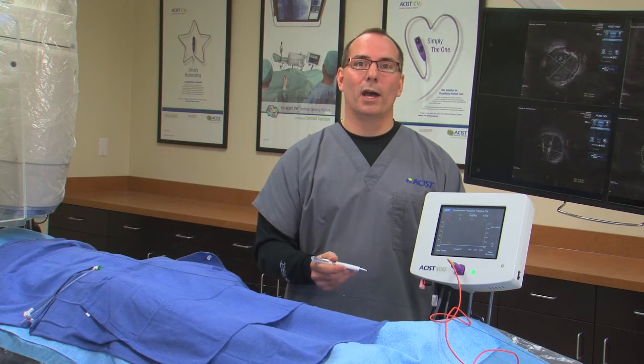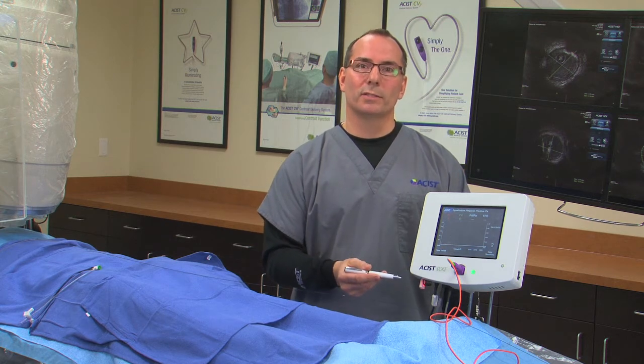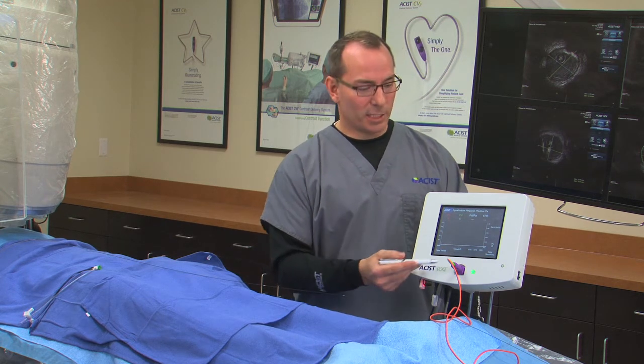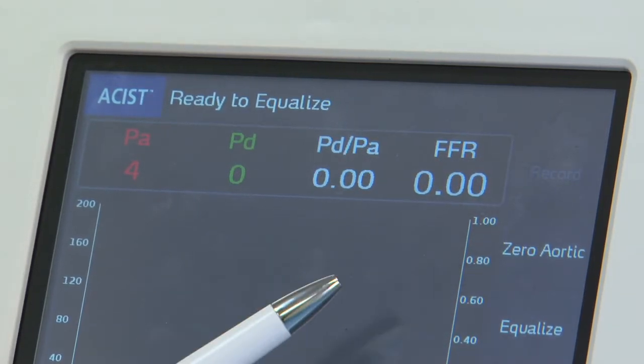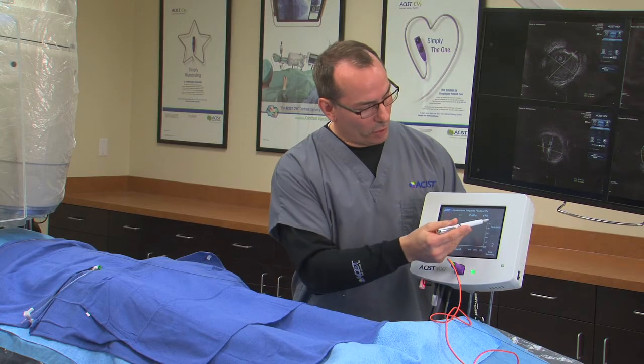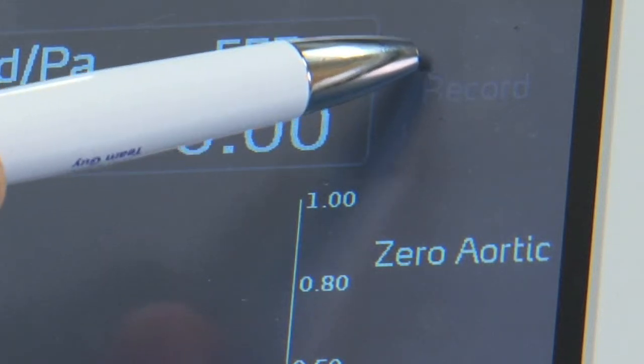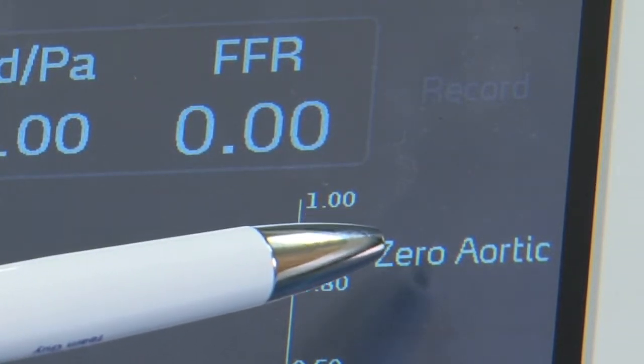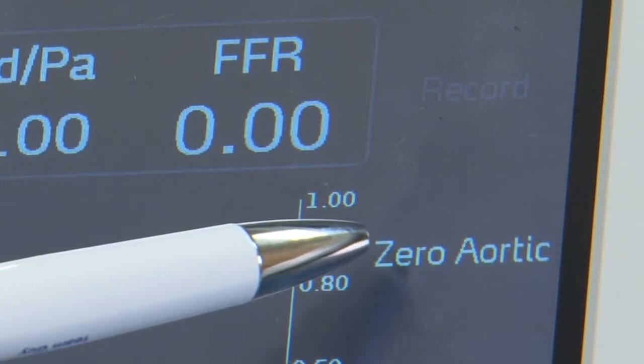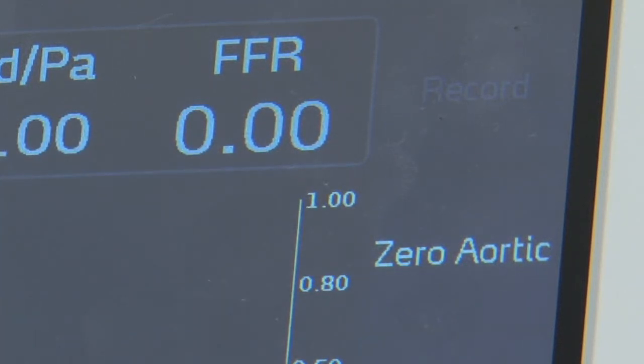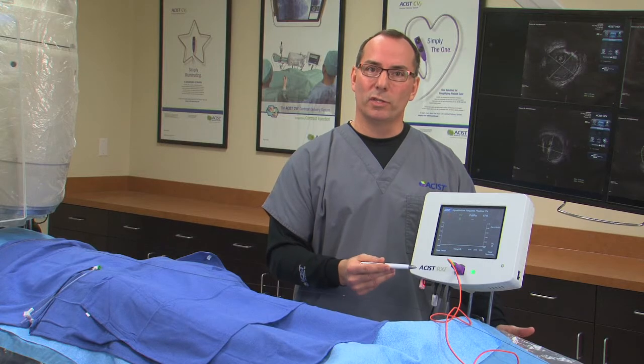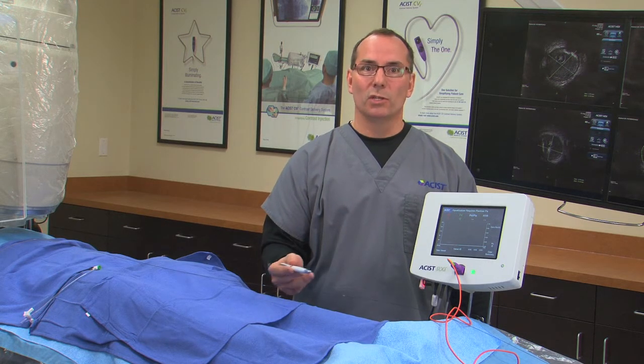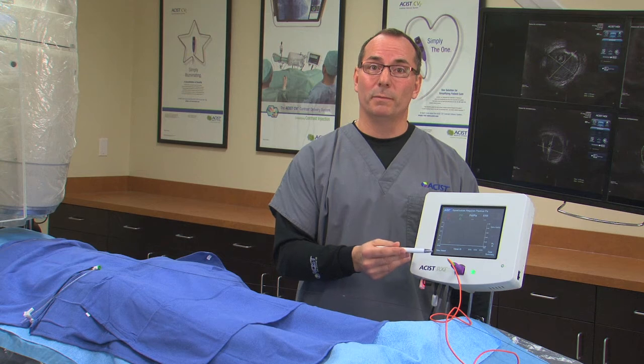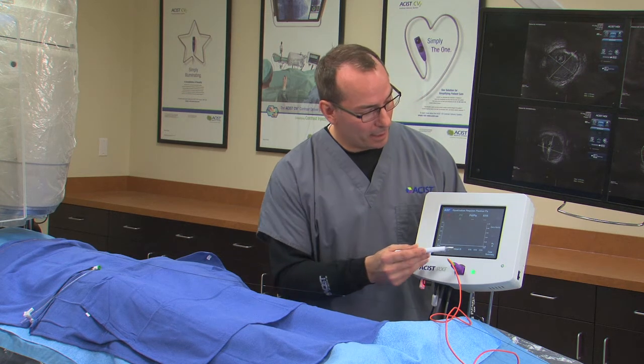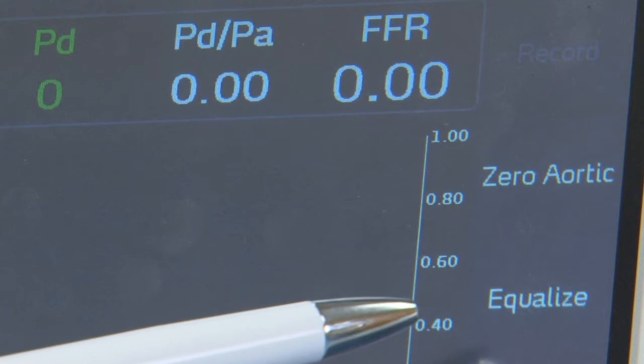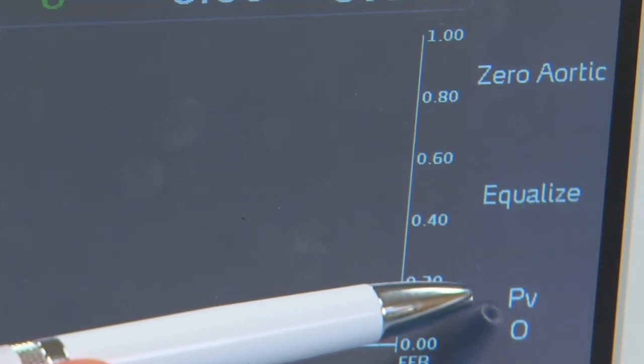When recording, the RXi Console will track the pressure gradients, calculate the FFR, and display the value here under FFR. Working around the screen, the record button records the hyperemic response, then is the zero aortic button. Now the zero aortic button is only used at the time of install. Then we pair or match this system with the hemodynamic system, so you no longer have to zero the system unless you choose to. The next button is the equalize button, followed by the PV button.